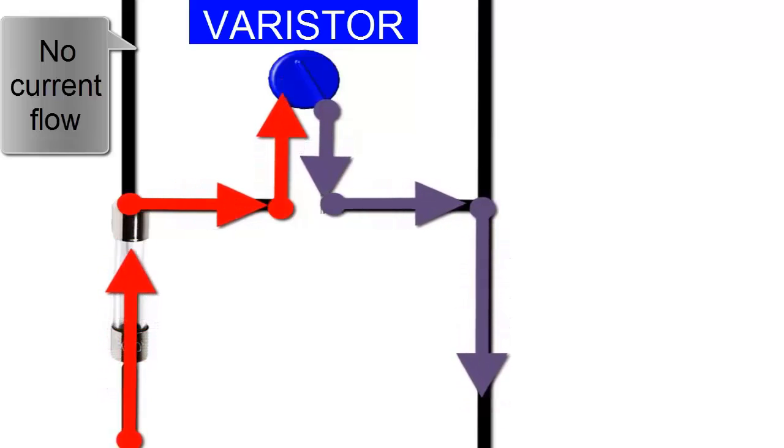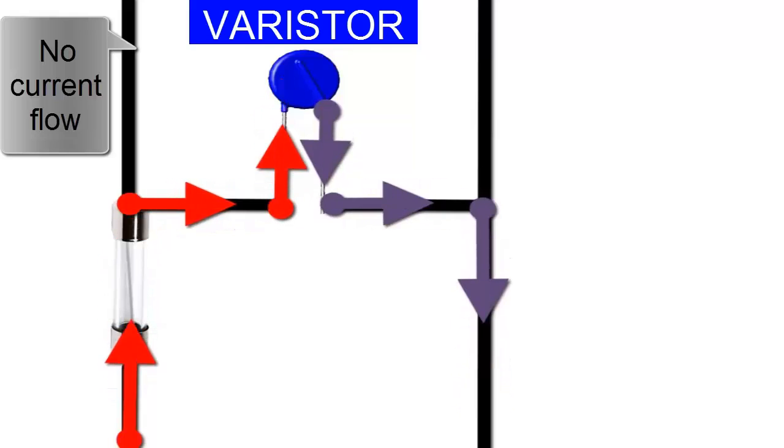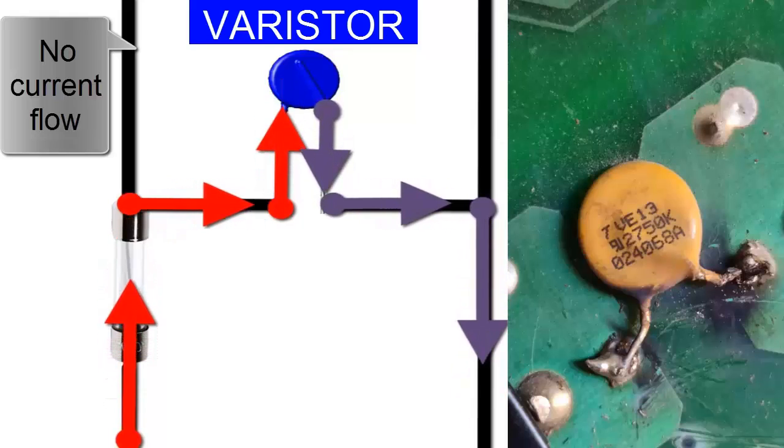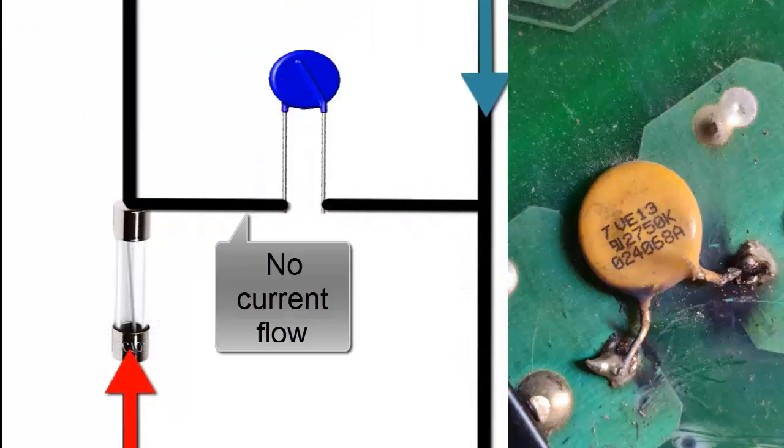It's important to note that the varistor only suppresses transient spikes. If exposed to a constant high voltage, it degrades or becomes damaged, as when 230 volts are applied to a varistor designed for 110 volts.